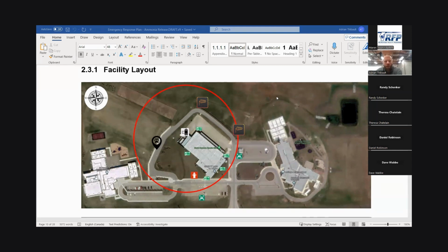A question from Andrea. With our new plant with a very low ammonia charge, 60 pounds, do we have even a potential of emergency? Very, very low potential at that point. Yeah, you probably have a plate and frame chiller. I love that system, how they're doing that. I think that's the next chiller we're going to go with at Lifespan.